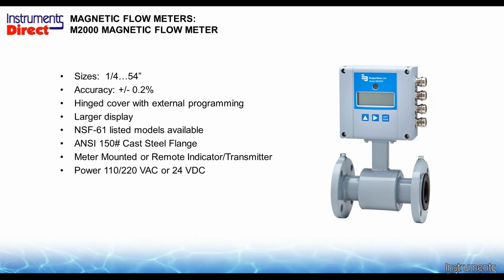The accuracy of the M2000, as I said, is pretty much our workhorse flow meter there, about 0.2%. The basic device has a hinge cover with external programming, very large display. So we said NSF 61 listed models. The basic model comes with 150-pound cast steel flanges there. You can either get it remote or integral. You have a choice of selecting either AC or 24-volt DC power.